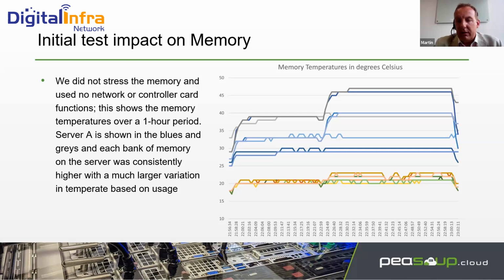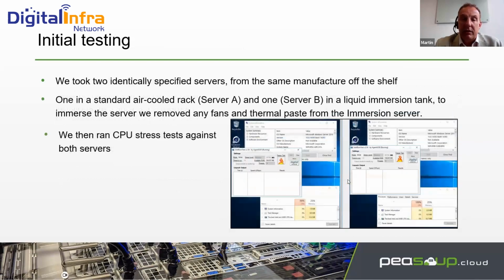Here we started to see a big differential. Anything in the blues and greys is air-based, and anything in the greens, yellows and browns is liquid. What we get is much tighter control in liquid. The liquid we used was about 20 degrees since we put it in a standard data center, so what we're getting in is quite low, but the tighter range between the two meant we could push that baseline temperature up because we're not getting as much spread.